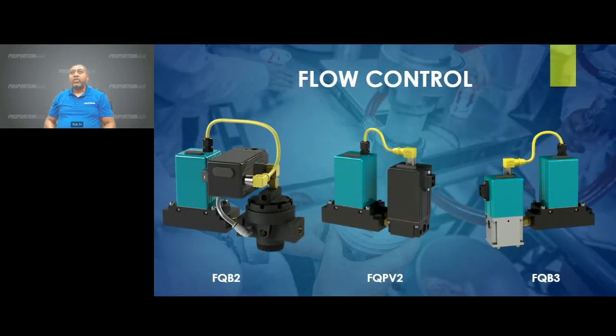Our mass flow series comes in 3 options that mirror our EPRs. Flow measurement happens in under 10 milliseconds. The FQB2 offers 25 SCCM maximum flow, and the FQPV2 handles a maximum flow range from 1/3 to 1 SCFM, and the FQB3 covers from 2.5 to 25 SCFM maximum flow. 3 models are available as well.